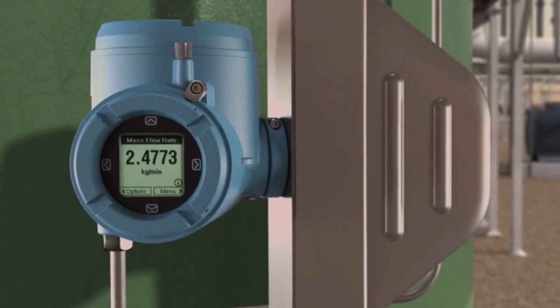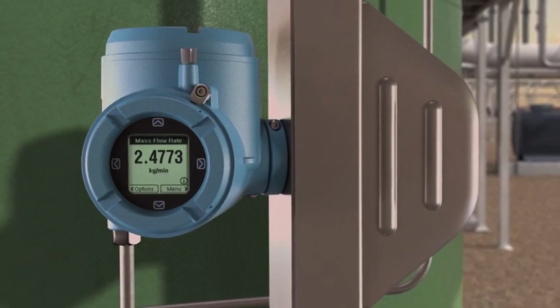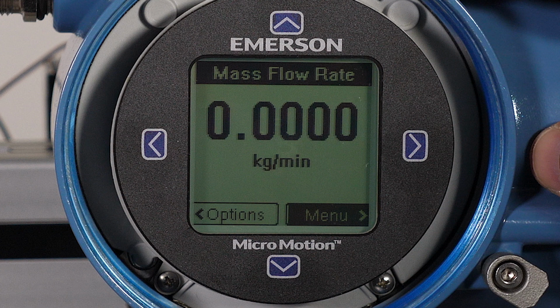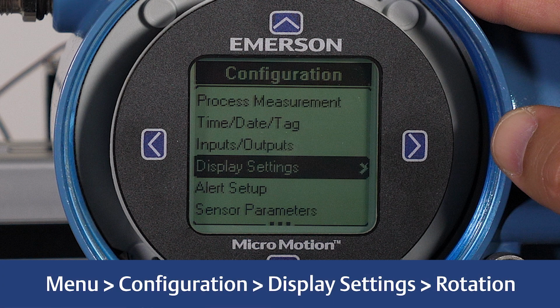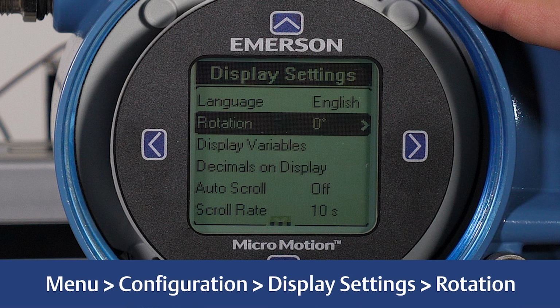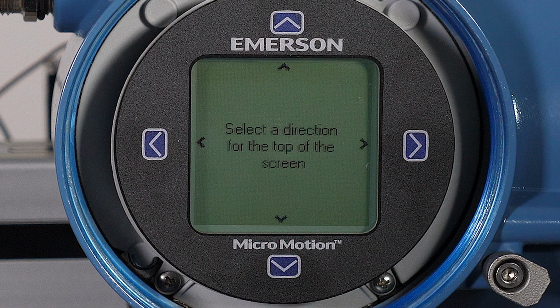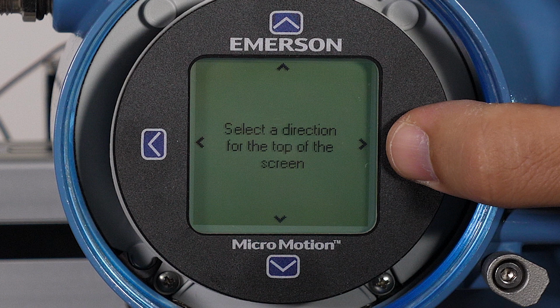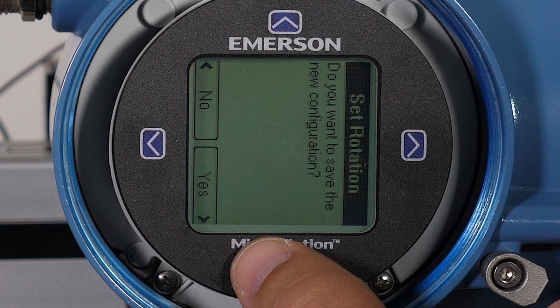The 4200 transmitter display can be rotated without having to physically remove the display or front cover. To rotate the display, select Menu, Configuration, Display Settings, Rotation. Then, using the arrows on the screen, select the direction for the top of the screen and confirm the new configuration by selecting Yes.